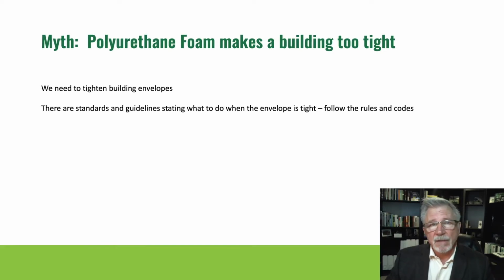When we tighten the building envelope down in the ranges of 1, 3, 5 air changes, we can downsize our HVAC and save some money, but we must also add the ERV, HRV to regularly pass that indoor air over top of those cooling coils so that we can pull the moisture out. It's very important. Now, there are products out there that can take 1 air change and make it 0.001. That's a very tight building envelope. Some of the conversation in the code industry, in the code community, is that all buildings should be built to a level of 1 air change.